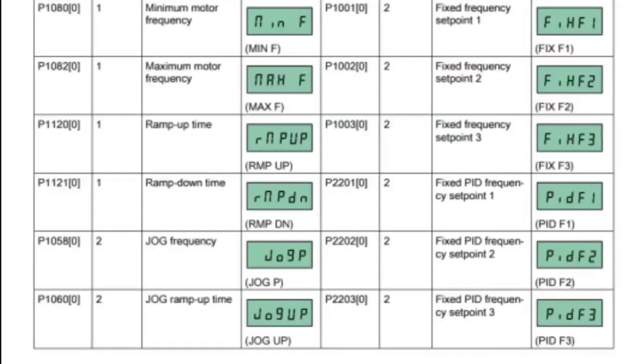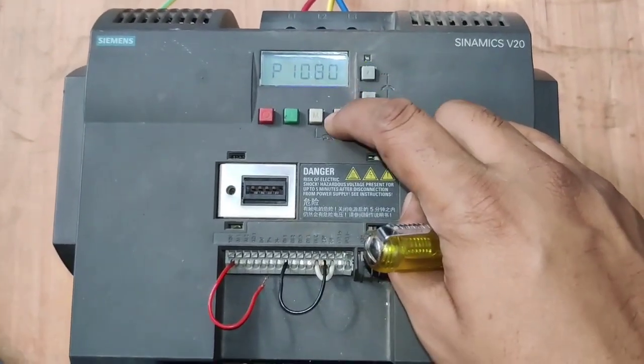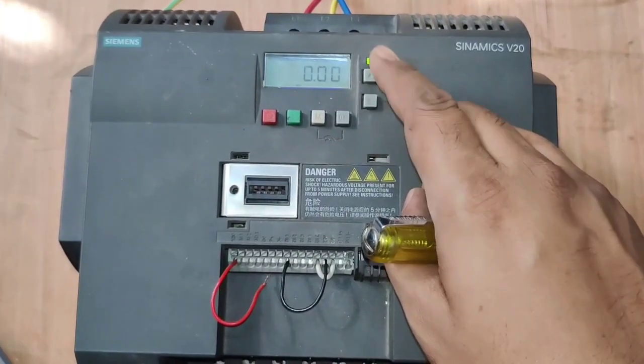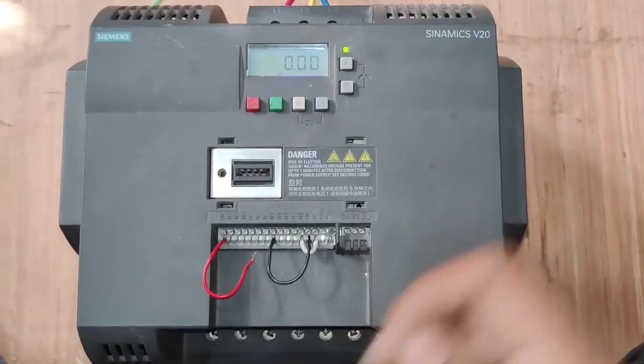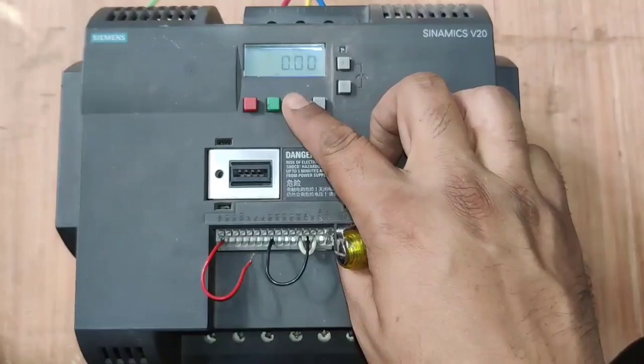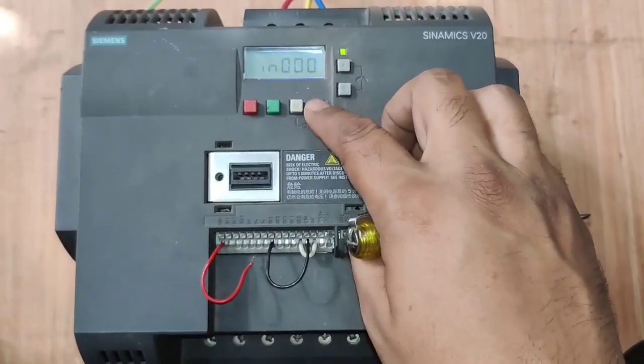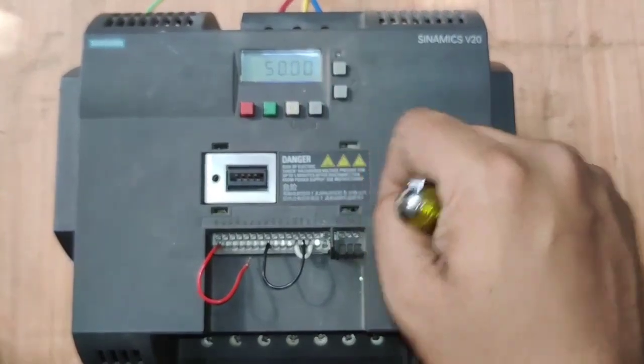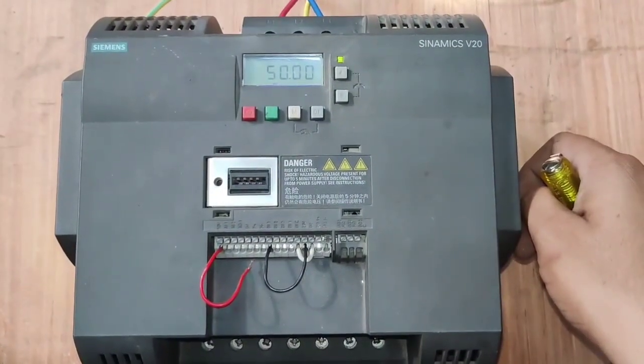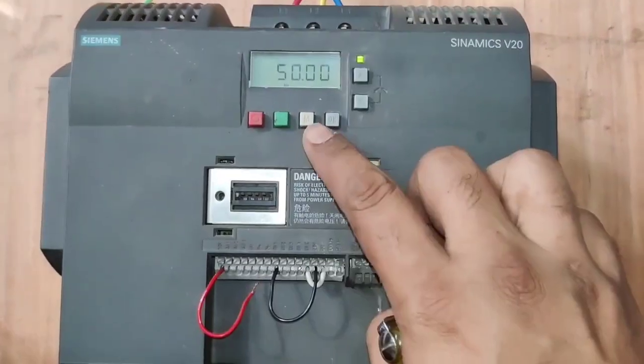Next parameter is P1058, which is jog frequency. If you want to start your motor with a jog command, you just need to set P1058. Next parameter is P1060, which is jog ramp-up time. Next parameter is P1080, which is the minimum frequency when you start your drive. When your drive starts at zero frequency, we set the minimum frequency to 0. P1082 is the maximum frequency. In maximum frequency we set 50. You can adjust your frequency according to your application.